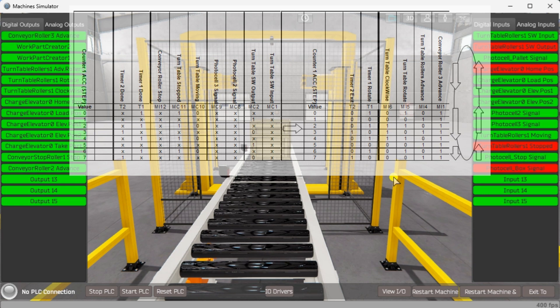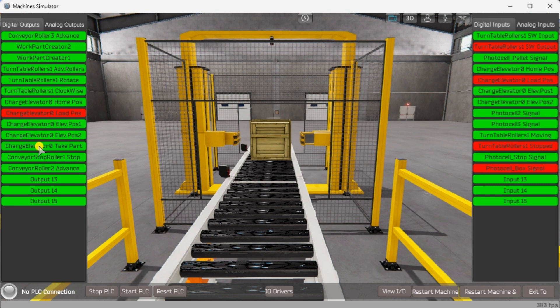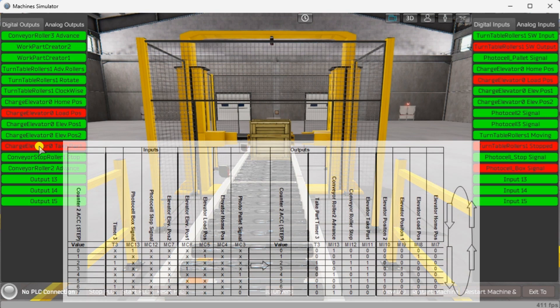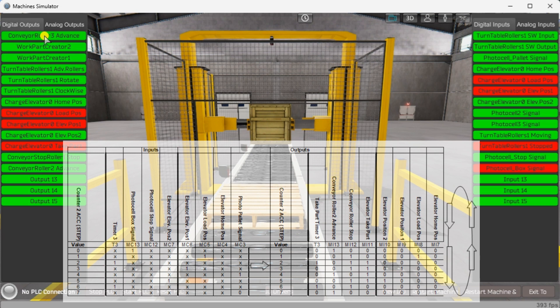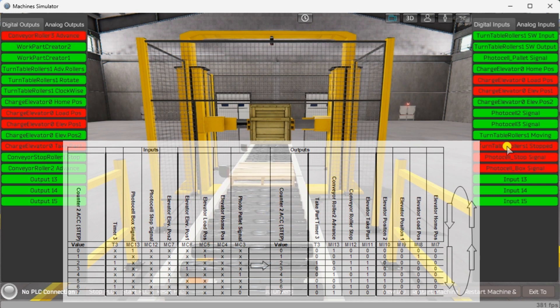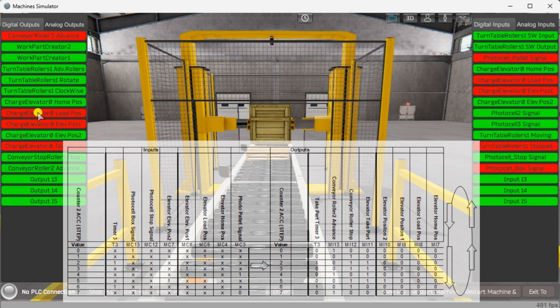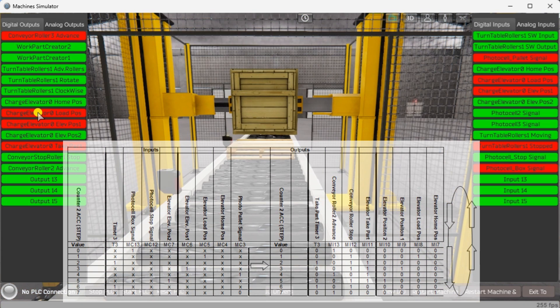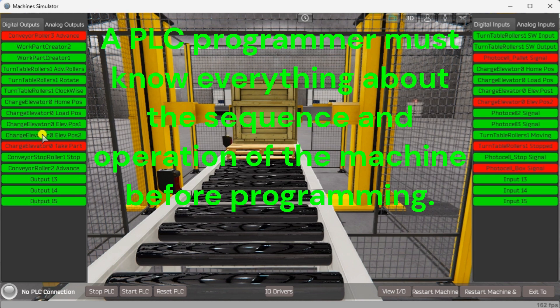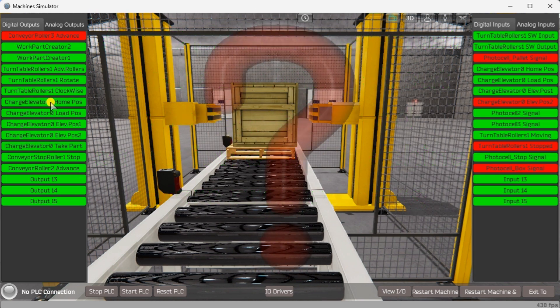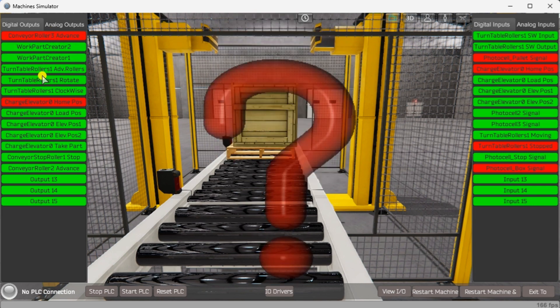Counter 2 controls the sequence of the elevator. Once again, the input signals are on the left side and the output signals are on the right. The value of the counter is shown with each step. We can move to the next step if the counter value is zero and we have the box signal. The conveyor roller 2 advances when the output activates at counter value zero. Repeat the process for all the other counter values until the last one of seven, which resets the counter back to zero. A PLC programmer must know everything about the sequence and operation of the machine before programming. Ask questions or review existing documentation to ensure that you know the logical steps to the machine's operation.